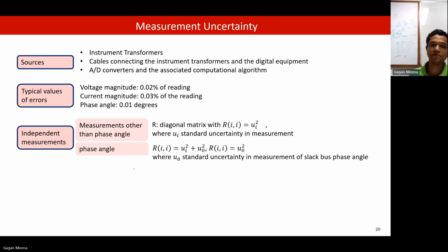Yes, state estimation only. So here, measurements other than phase angle are considered as independent. Therefore, the weight matrix for them becomes a diagonal matrix, where the diagonal entry is equal to u_i square, and u_i is equal to delta u by root 3, where u_i is the standard uncertainty in the measurement.